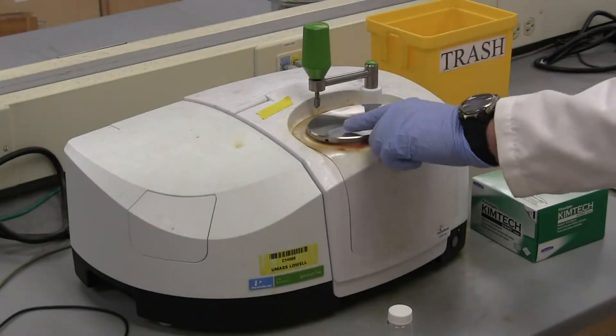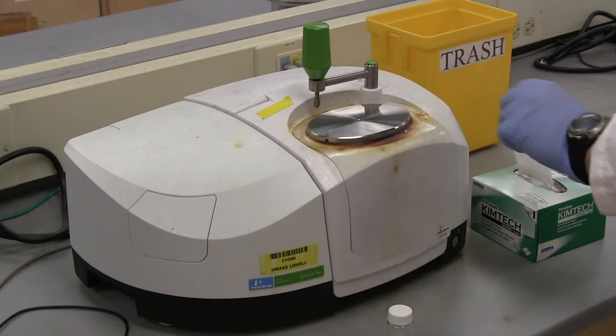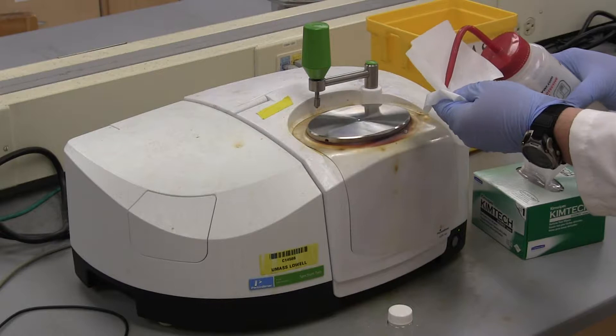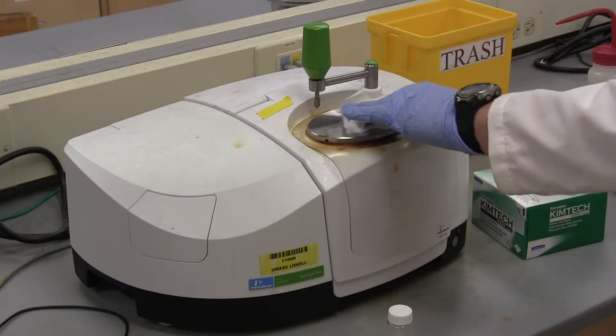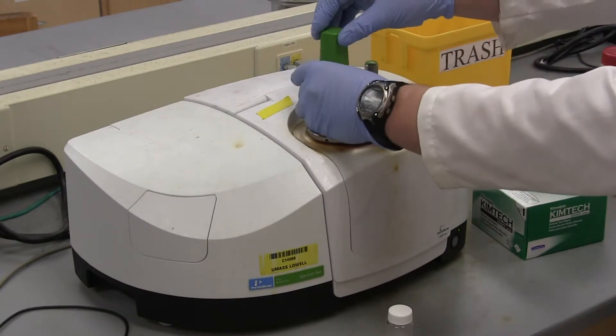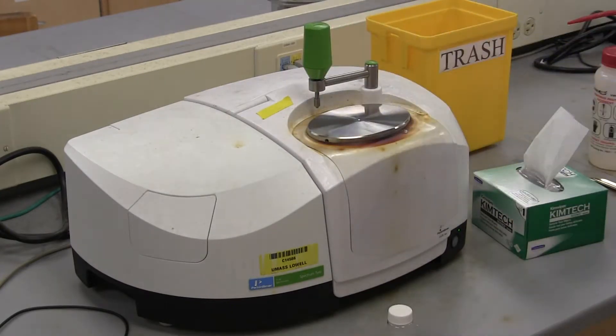The first step is to clean the zinc selenide diamond crystal as well as the tip of the arm with acetone. Simply squirt a little bit of acetone onto a kimwipe and wipe it on the crystal. Do not drip acetone onto the instrument though, since acetone will dissolve the plastic.